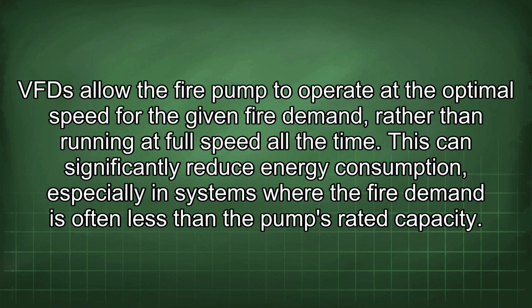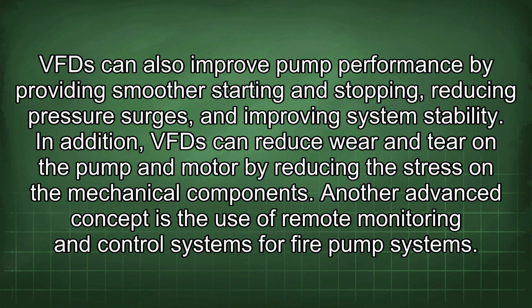This can significantly reduce energy consumption, especially in systems where the fire demand is often less than the pump's rated capacity. VFDs can also improve pump performance by providing smoother starting and stopping, reducing pressure surges, and improving system stability. In addition, VFDs can reduce wear and tear on the pump and motor by reducing the stress in the mechanical components. Another advanced concept is the use of remote monitoring and control systems for fire pump systems.